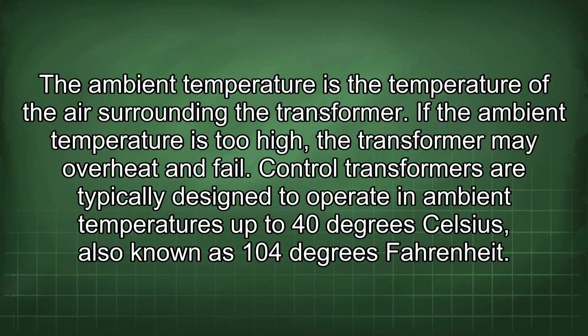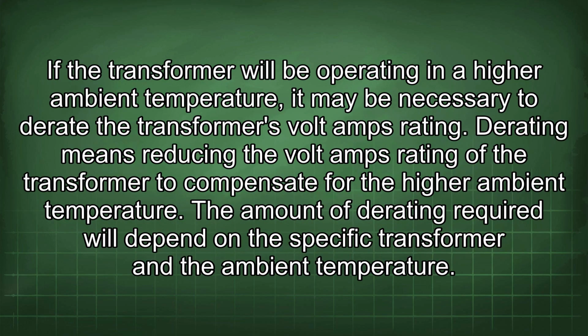If the ambient temperature is too high, the transformer may overheat and fail. Control transformers are typically designed to operate in ambient temperatures up to 40 degrees Celsius, also known as 104 degrees Fahrenheit. If the transformer will be operating in a higher ambient temperature, it may be necessary to derate the transformer's volt-amps rating. Derating means reducing the volt-amps rating of the transformer to compensate for the higher ambient temperature. The amount of derating required will depend on the specific transformer and the ambient temperature.